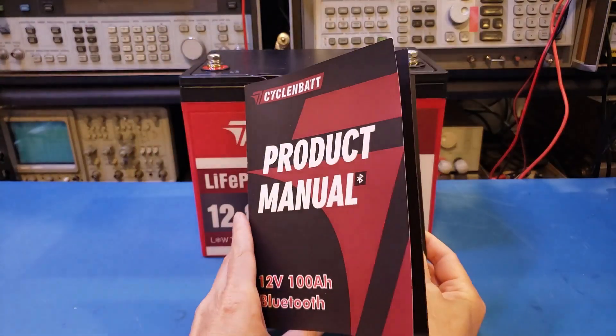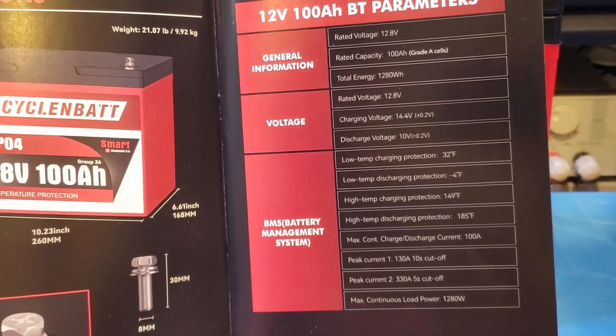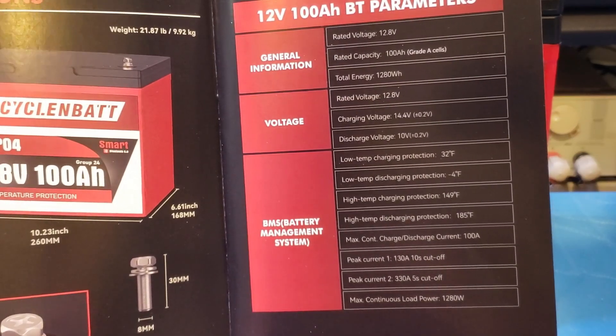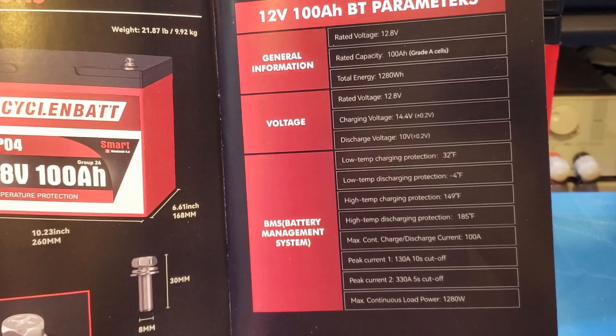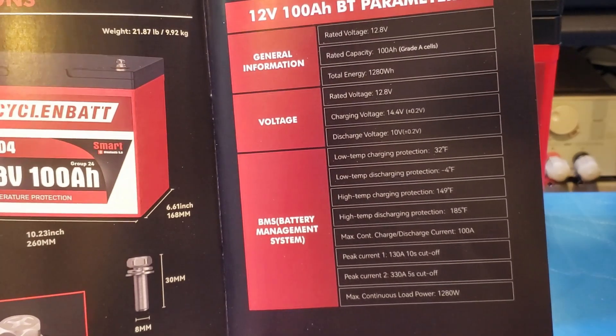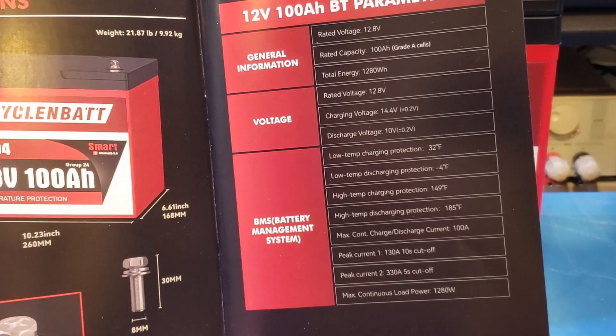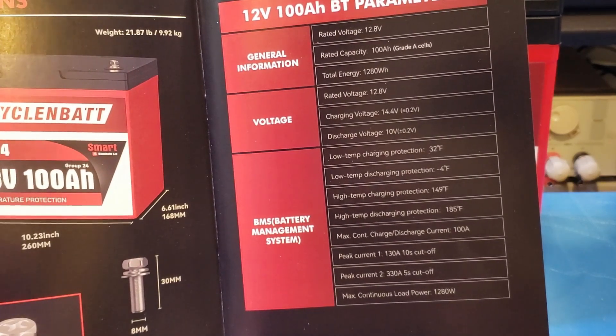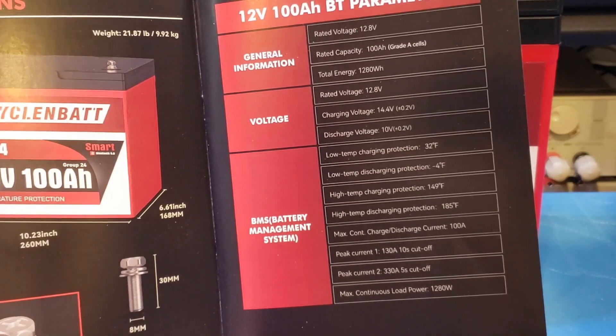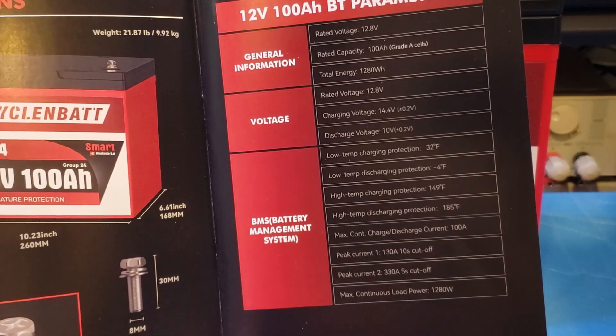The product manual is fairly comprehensive and similar to what's provided with other CyclenBatt batteries. From the specifications, you can see that this battery has low temperature charging protection, which would cut off the charging current if the core temperature is below freezing. LFP batteries should not be charged below freezing as it would cause permanent damage to the cells. The BMS also has low temperature discharge protection, and high temperature charging and discharging protection as well, which gives you peace of mind.